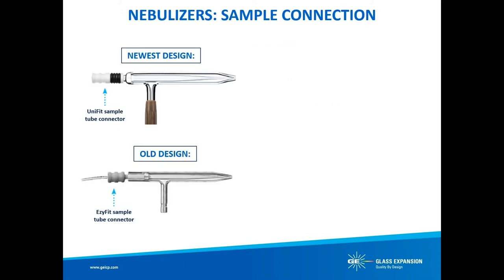Let's start by looking at some connections that are common to nearly all ICP configurations. The U-Series is our most up-to-date nebulizer design. It has a UniFit sample connector which easily slides over the sample inlet, in contrast to the EZ-Fit sample connector which slides into the nebulizer sample arm. It resists blockage — the sample channel is uniform from the entry point to the tip, so there's nowhere for particulates to be trapped.